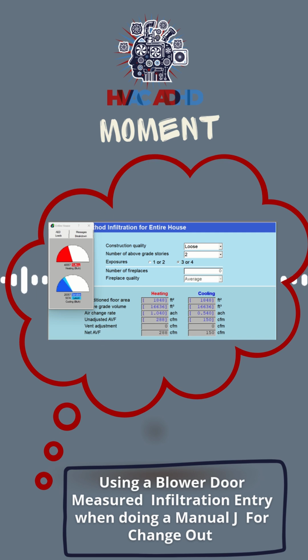Service both the quote unquote cold weather heat pump, service the heating load. I think those inverter heat pumps top out around 48,000 BTUs. Probably have enough turndown on the cooling load to feel comfortable and service this cooling load fully as well with the same piece of equipment. But that's using loose. Let's take a look at what happens when we use our blower door entry.